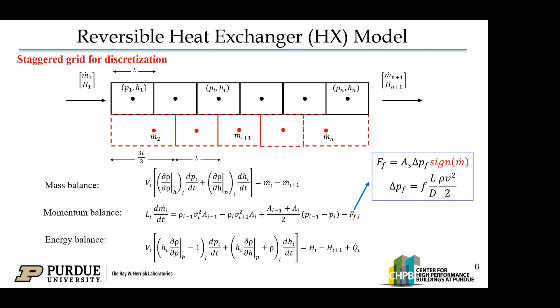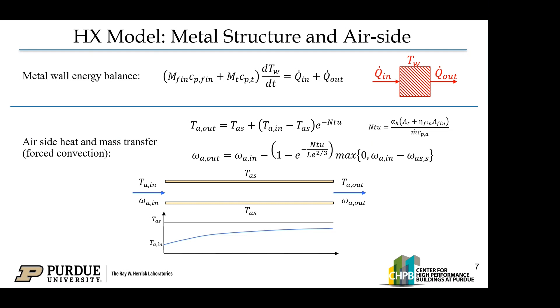Because friction is in the opposite direction to flow, we apply a sign function for the friction term. For the metal structure, we assume a uniform temperature of the tube and associated thermal mass, with an energy balance. For the airflow, because this is a cross-flow configuration, we assume quasi-steady state and derive the temperature and humidity profile. Please note this is only used for forced convection when the fan is running; during defrost, the outdoor fan is off, so there's another set of equations for natural convection to avoid singularity when airflow is close to zero. So far, this is the heat exchanger model used for non-frosting conditions.